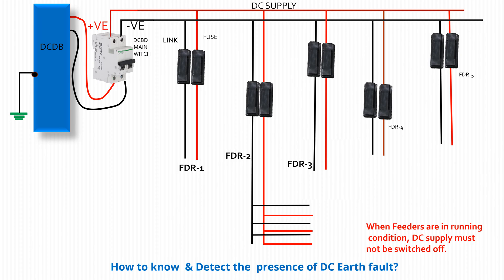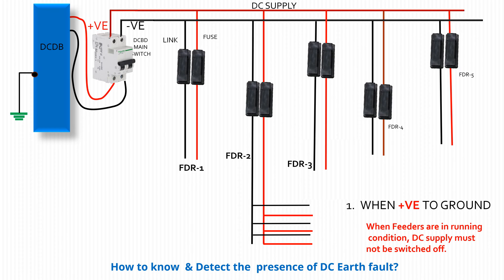In this section, detection of positive earth fault is shown here by animation to give a simple overview on this subject. It was seen in many cases that without using a fault locator, fault detection by this process was easier. This was the process of detection of DC earth fault by using a multimeter. DC negative earth fault may be detected by the same process.